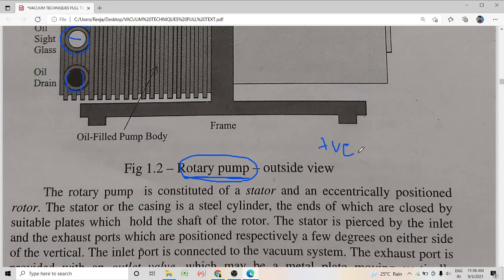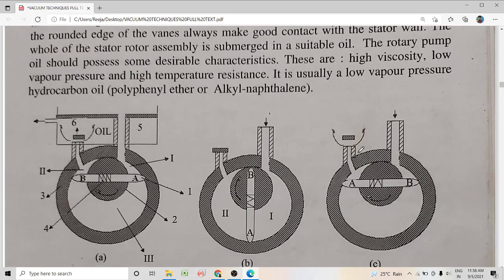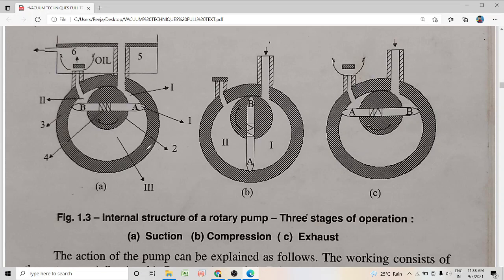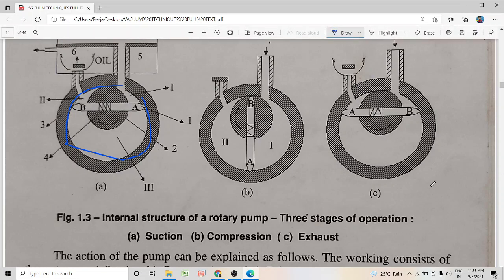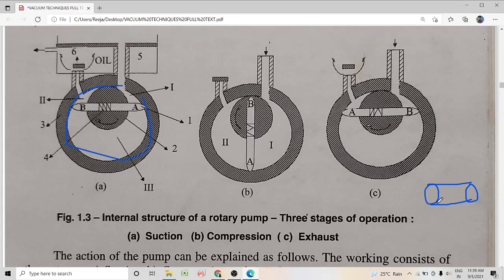What are the parts of a rotary vane pump? The rotary vane pump consists of two main parts: one is a stator and the other one is an eccentrically positioned rotor. The stator is the outer cylinder — you are seeing a top view of the rotary pump. The stator is a steel cylindrical chamber.